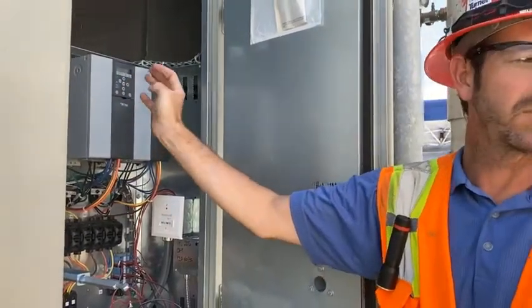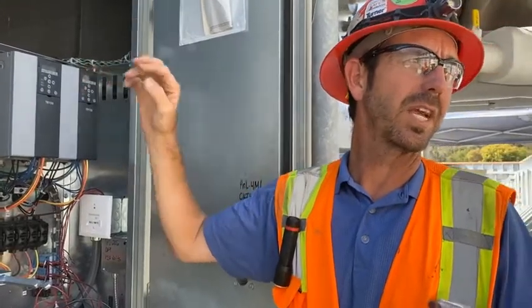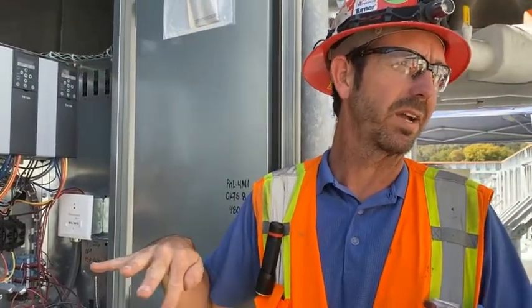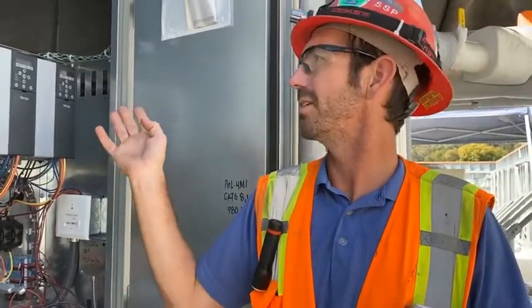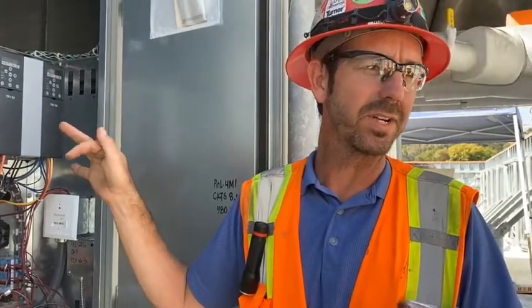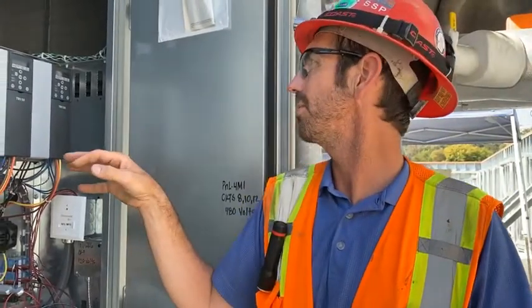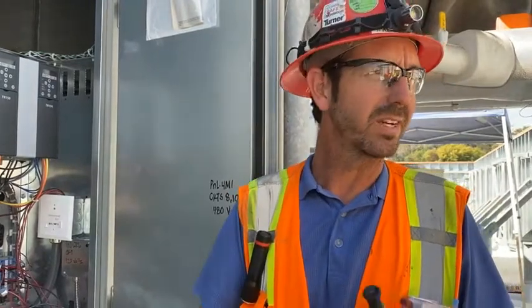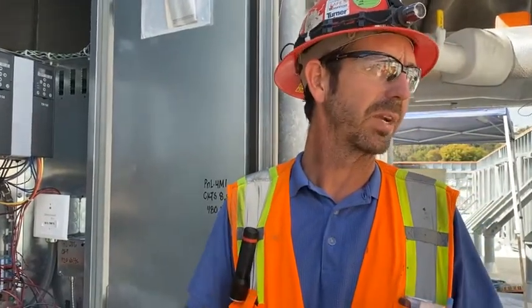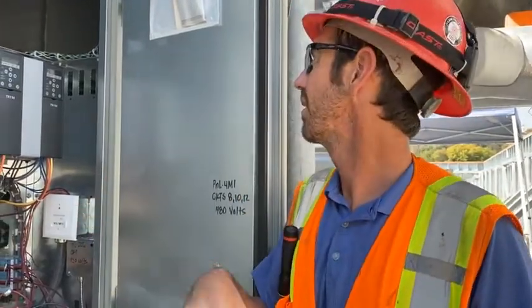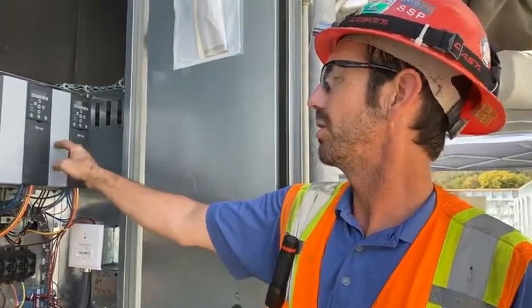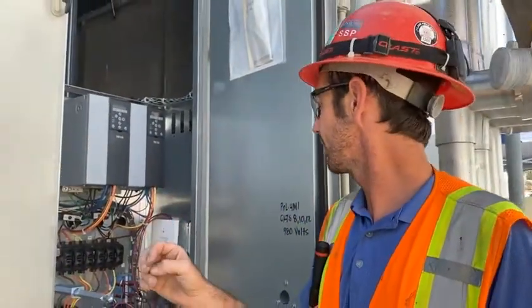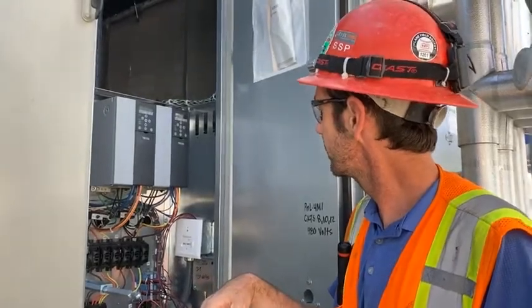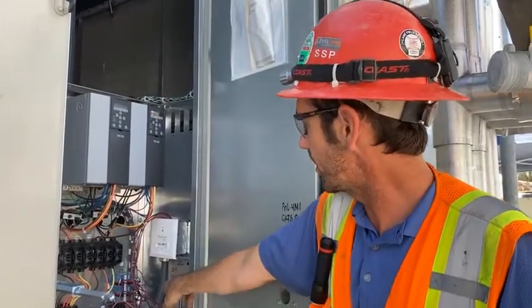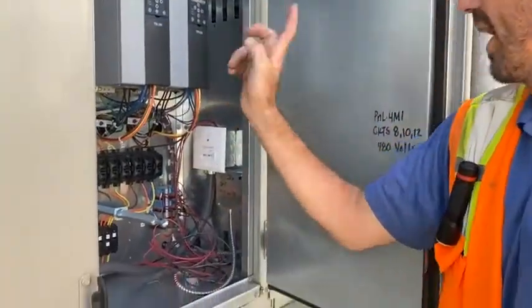Common options, these units are set up for Modbus. That's the communication that Sunbelt is using out here. So the units are set up for Modbus and have an address number associated with them. On each one of the main controllers downstairs, it needs a unique address, so be cognizant of that. Each one of these units will have a different address. This will be a junction box for the 120 volts that feeds the lighting panel.